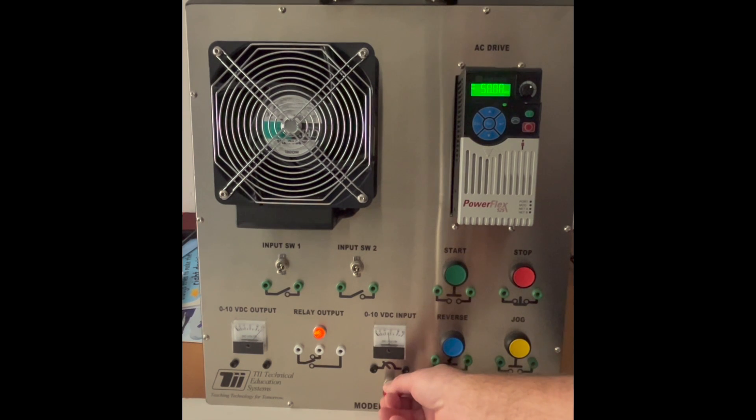So if I go to roughly 5 volts here I should be pretty close to about 30 hertz and I'd be running the motor at half speed. And so now an operator can come here and adjust this to control the speed of the variable frequency drive.